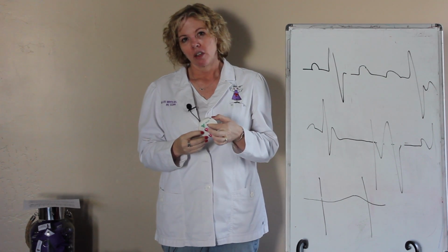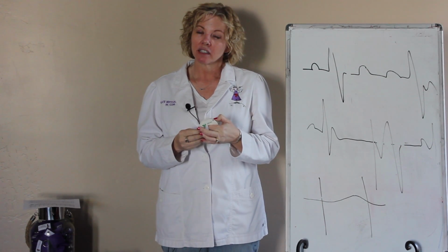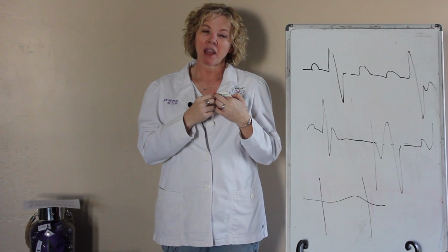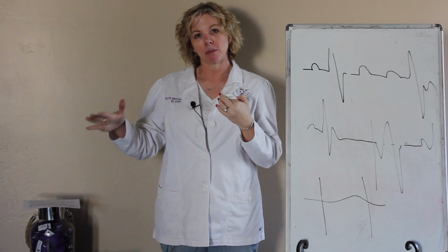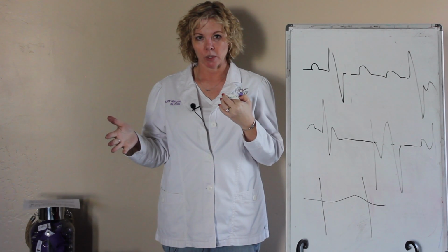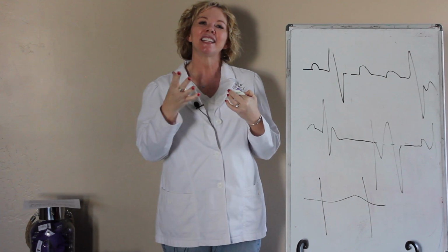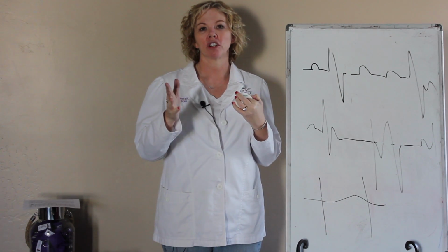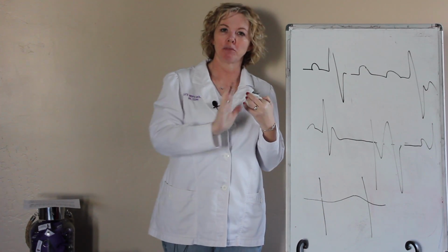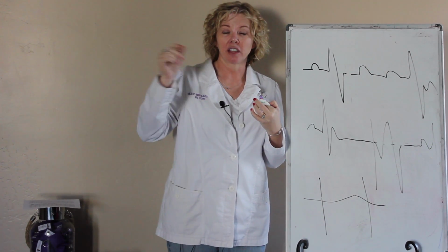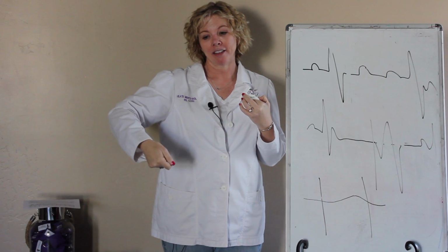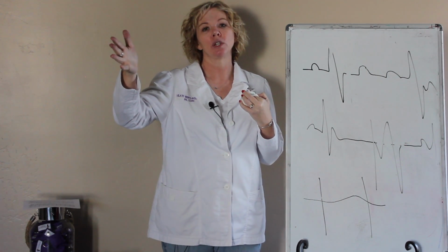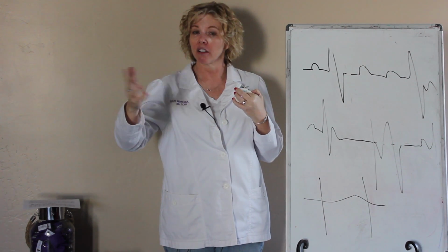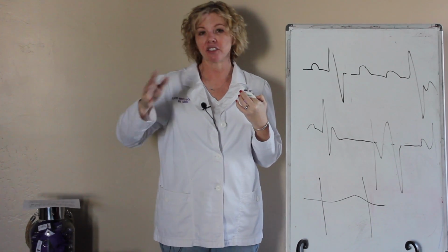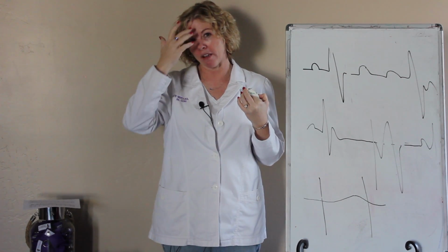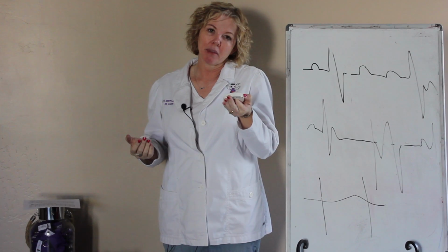That is not true. What a magnet does is stop the pacemaker from being able to see the intrinsic beats. So we say that it makes it asynchronous. It is no longer operating in synchrony with the patient's intrinsic beats. Think of that motion sensor light. It's as if I have flipped the switch and now that light is going to stay on, whether there's somebody there in front of it or not. I've just taken the sensing part away from it for a little bit. That is what a magnet does.